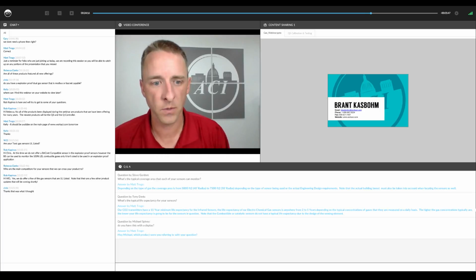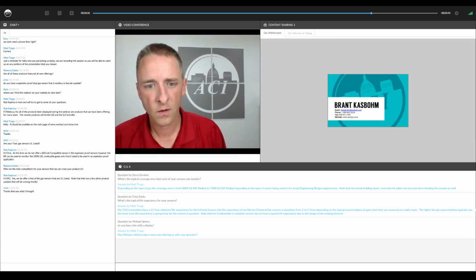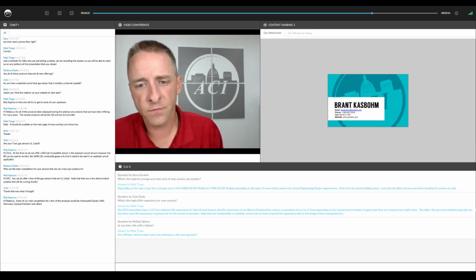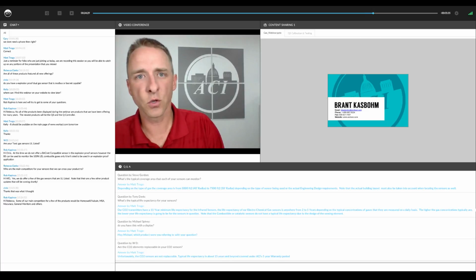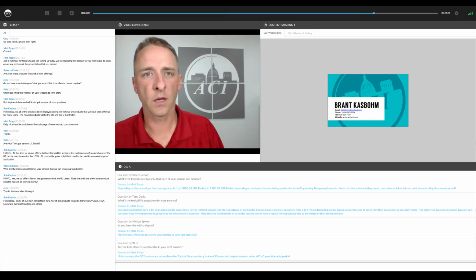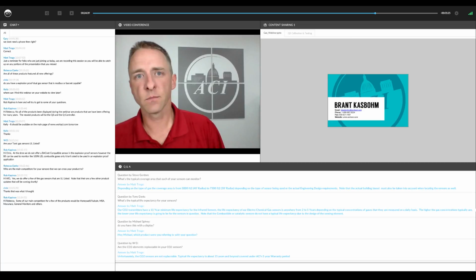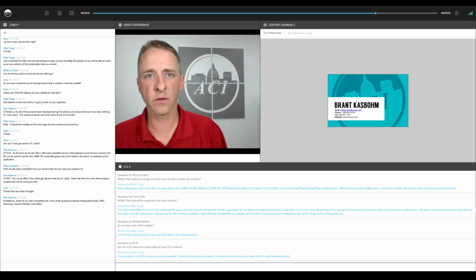Next question: how often should I check to see if the transmitter should be recalibrated? For CO2, if you're using the software, there's no need for future recalibration. For the toxic and combustible gas sensors, typically those do need to be recalibrated, and we don't have a hard and fast requirement for recalibration. That's more so on the specs of the job.